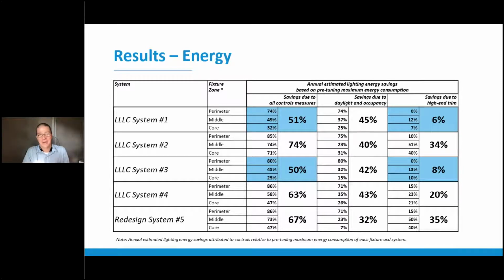So the first thing that we wanted to call out was that 2 of the 4 LLLC systems had pretty moderate high-end trim. They only saved between 6 and 8% energy savings from the high-end trim. That is basically getting to that question of how many lumens are installed relative to what is required to meet the 300 lux or roughly 30-foot candle threshold for the ambient illumination from the IES. And it just so happens that these 2 actually had slightly lower installed wattage, so they were a little on the lower end of the installed lighting power density in the first place.